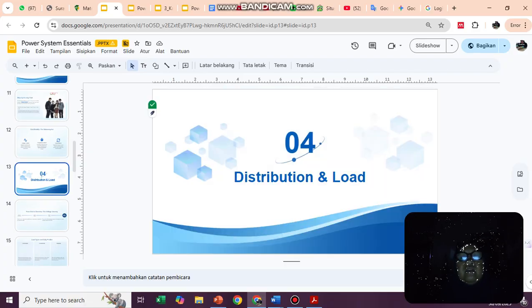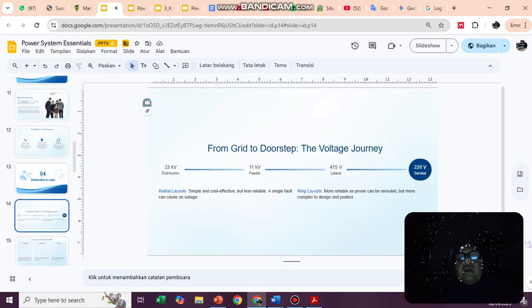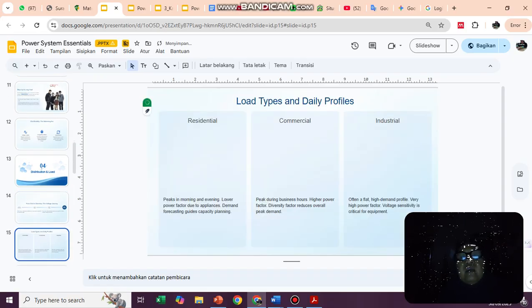And then distribution and load. From grid to doorstep, the voltage journey: 33 kV distribution, 11 kV feeder, and then 415 volt lateral, and then 220 volt service. Radial layout, simple and cost effective but less reliable. A single fault can cause an outage. A ring layout, reliable as power can be routed but more complex to design and protect.